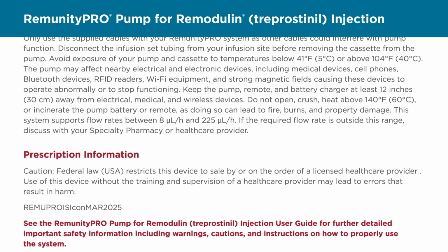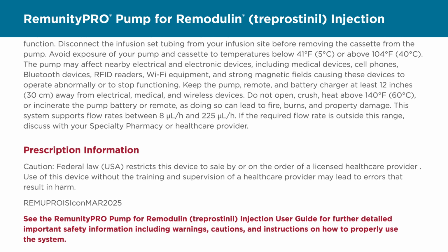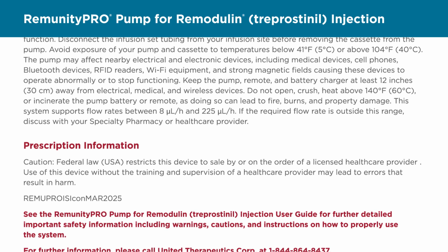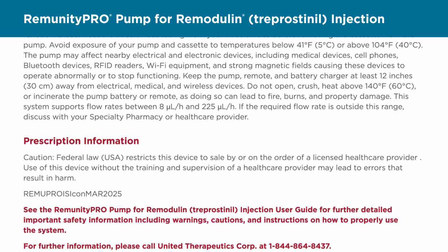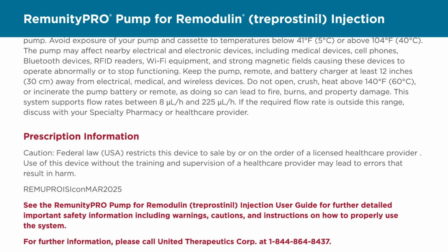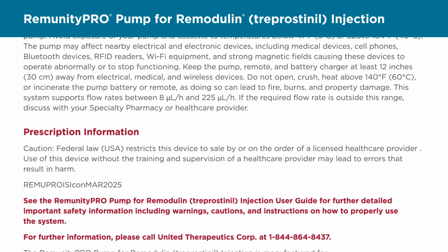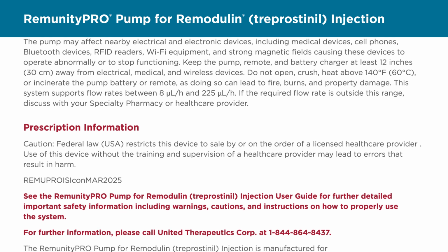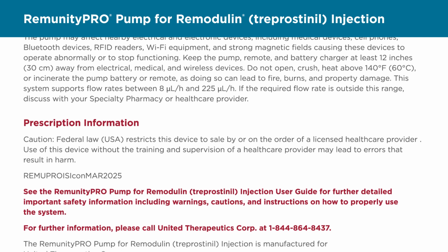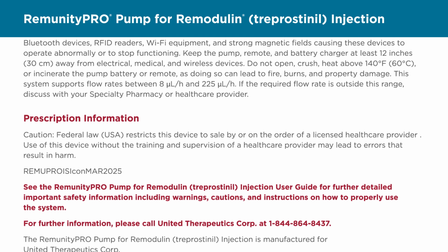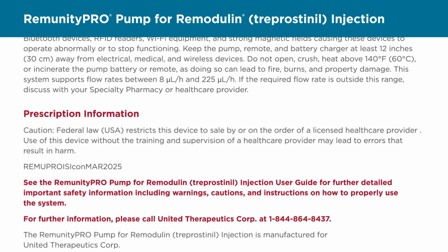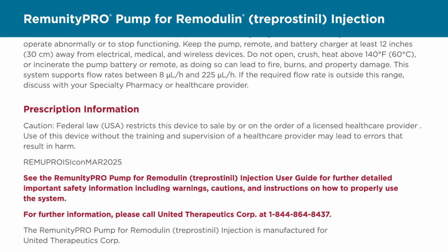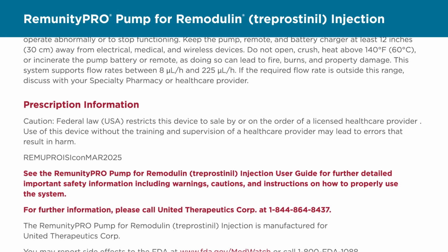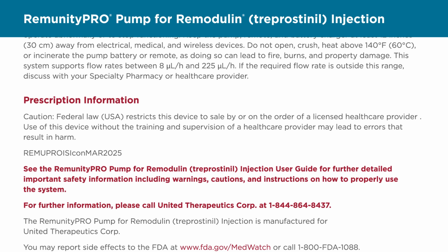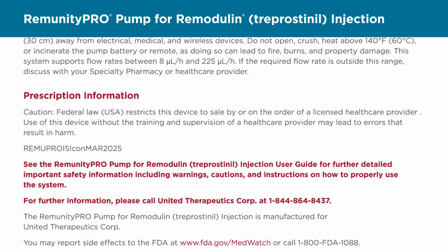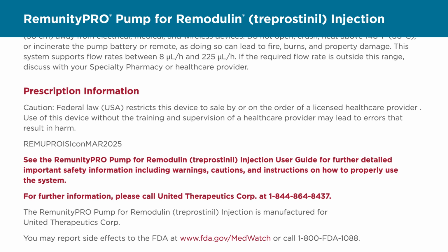This system supports flow rates between 8 microliters per hour and 225 microliters per hour. If the required flow rate is outside this range, discuss with your specialty pharmacy or healthcare provider. Prescription information. Caution: federal law USA restricts this device to sale by or on the order of a licensed healthcare provider. Use of this device without the training and supervision of a healthcare provider may lead to errors that result in harm. See the RemunityPRO pump for Remodulin treprostinil injection user guide for further detailed important safety information including warnings, cautions, and instructions on how to properly use the system.